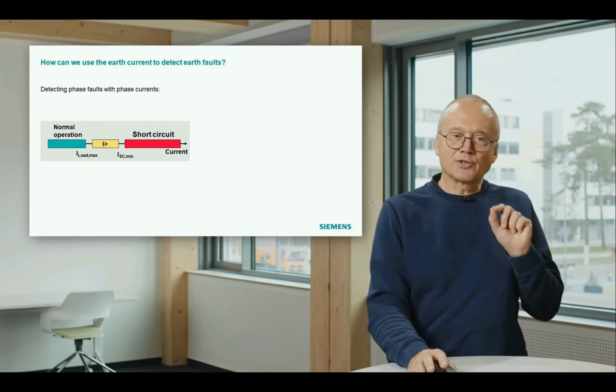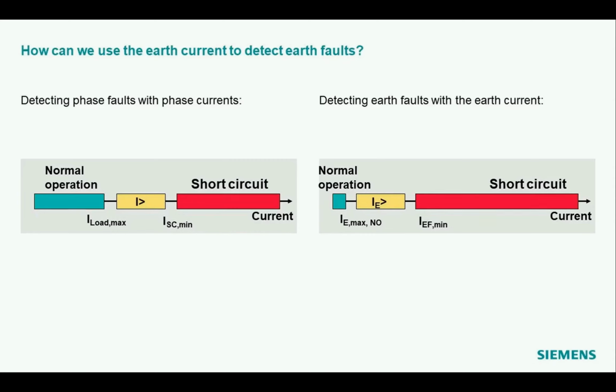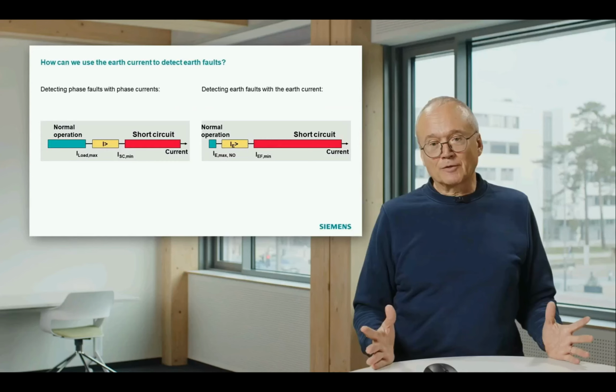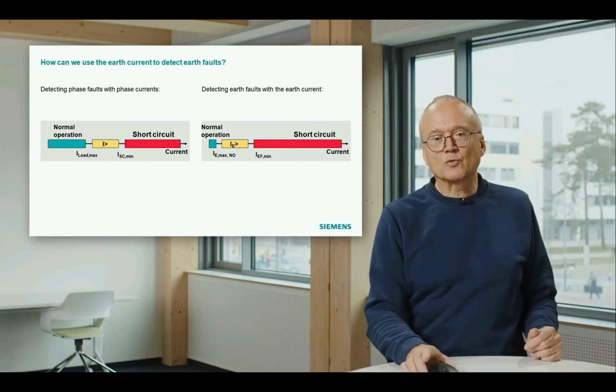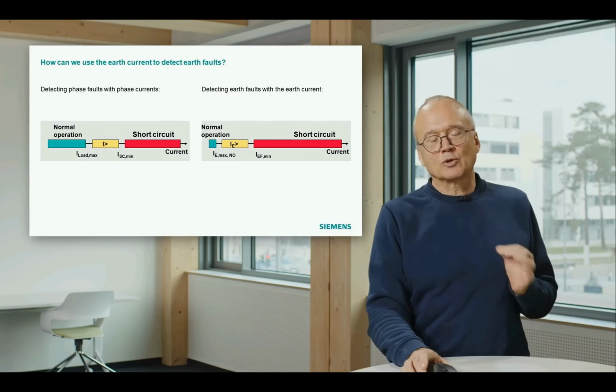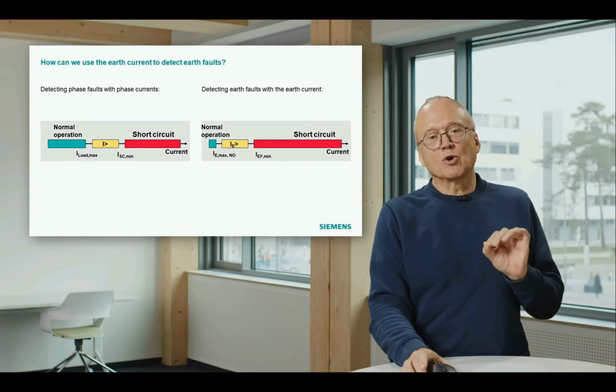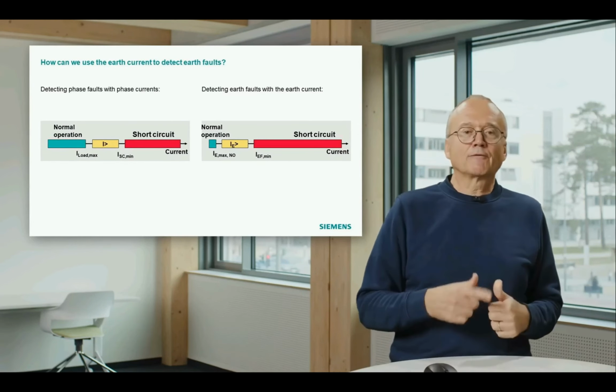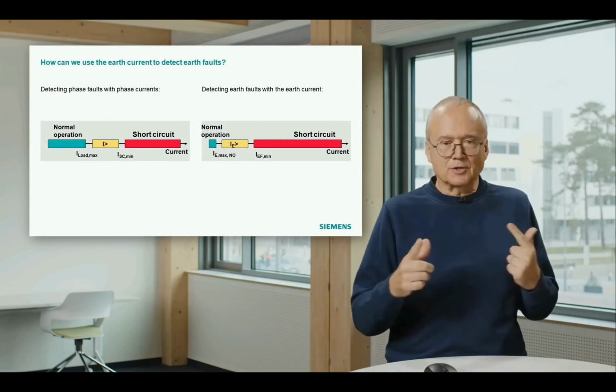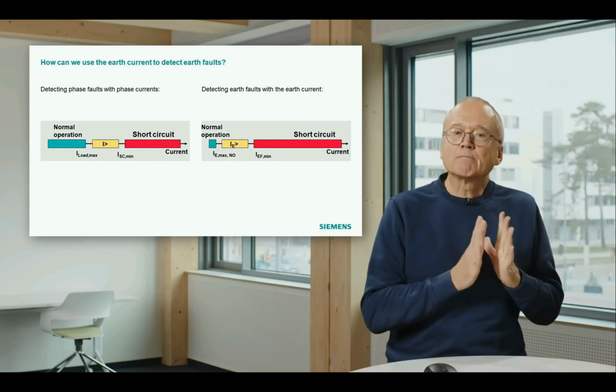Now, if we apply the same principle to the earth current, how does it look? The point here is the green area becomes much smaller, because on the left-hand side, the green area is defined by the maximum current we see under heavy load condition. If we look at the earth current, even with heavy load, we don't have much earth current. That means we must make up our mind only concerning the question, what is the maximum earth current we see resulting from unsymmetrical operation of the system plus CT errors, but that is much smaller.